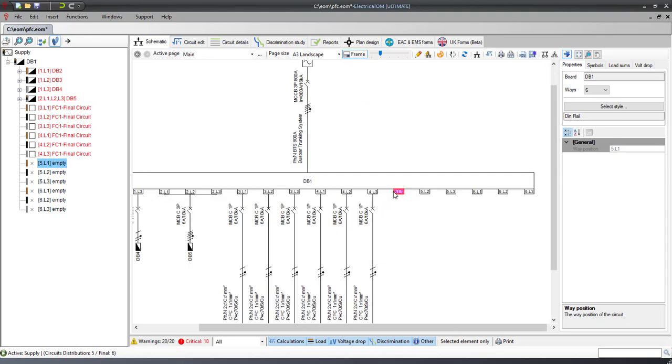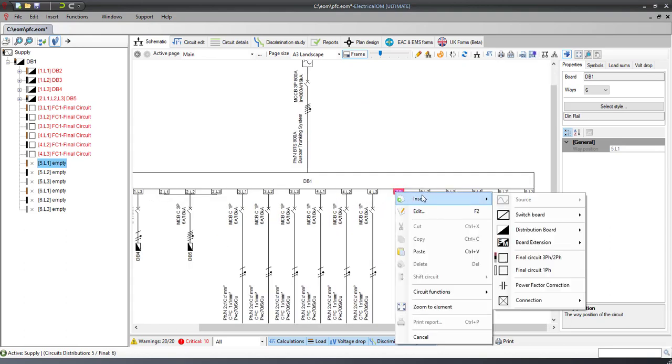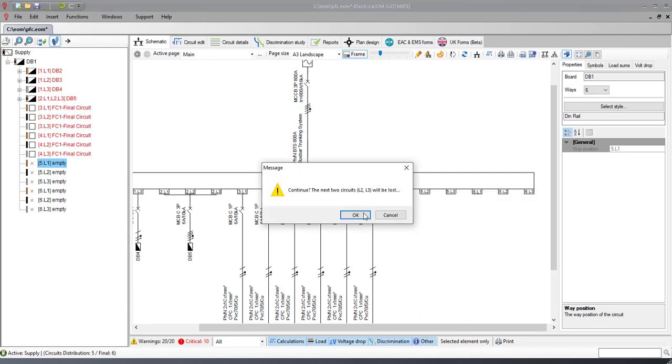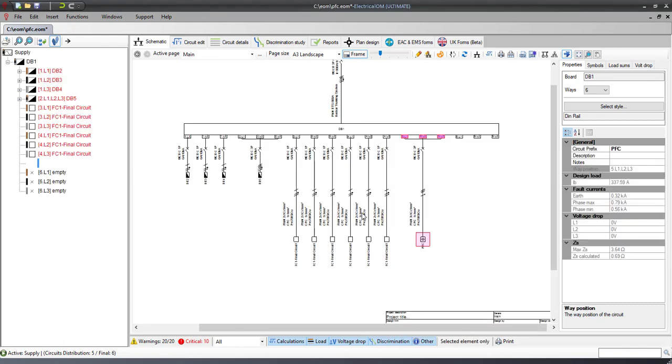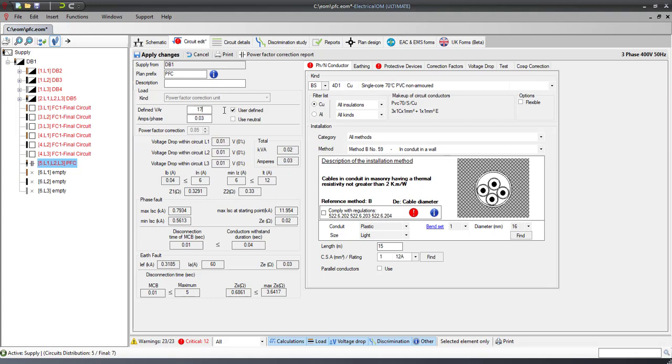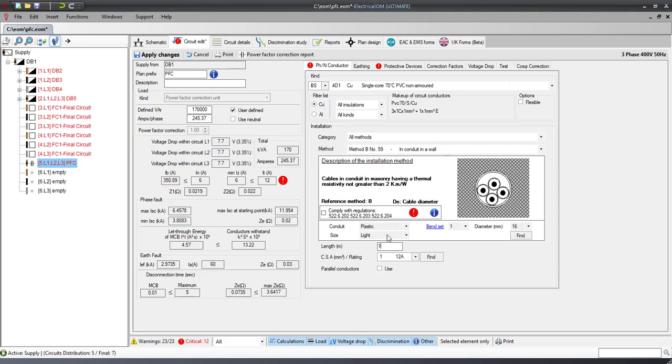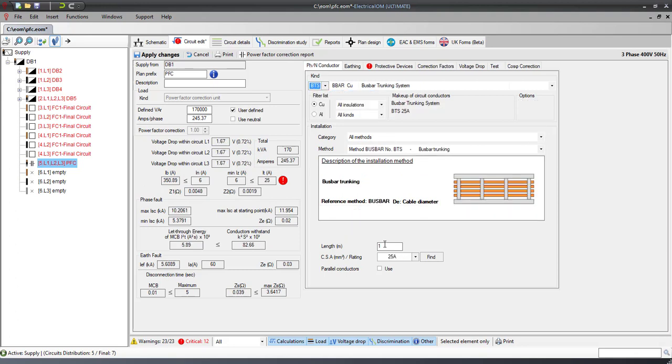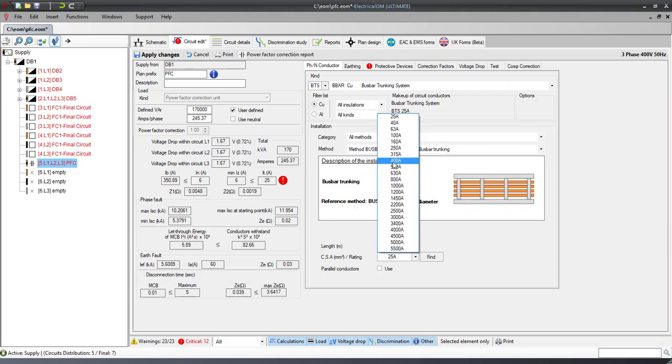First, insert the Power Factor Correction Unit. Then, based on the calculated size required for the correction, specify the user-defined size of the Power Factor Correction Unit. This will enable you to size the conductor and the protective devices based on the actual size of the correction factor used.